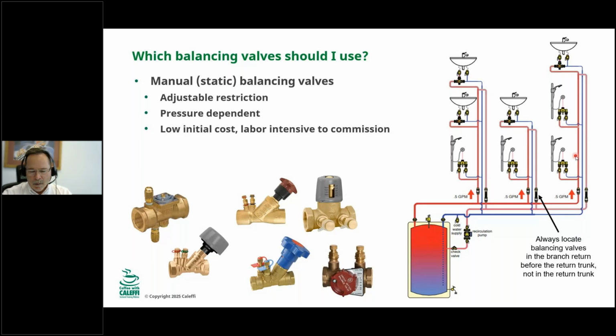Typically, they're lower cost to put in, but they're very labor intensive. And way too often we see pictures or have customers call in, contractors call in, and they find these wide open. They go into an existing building and, yeah, the valves were all wide open. Well, yeah, that's your problem. That's the problem. So they can work. They can work just fine if they're properly installed, properly tested.